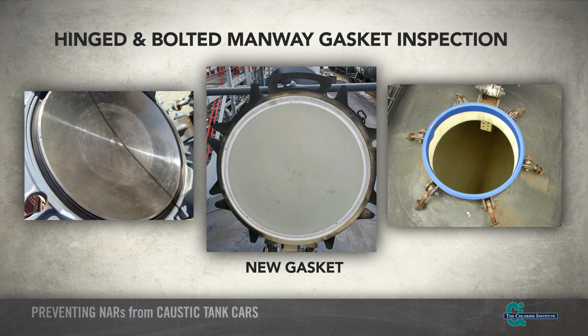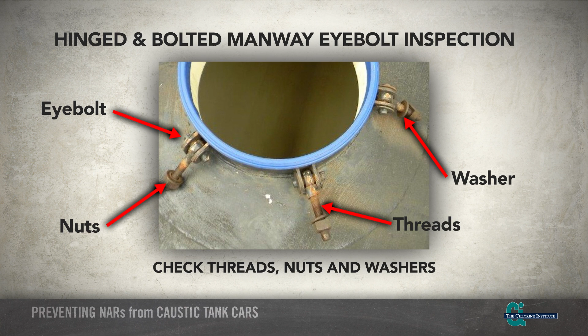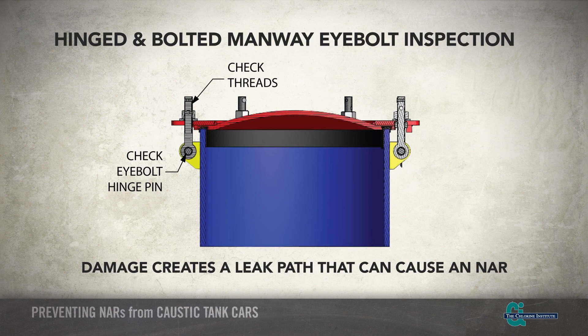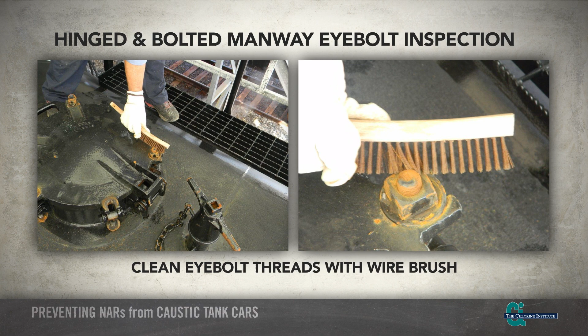Prior to closing the hinged and bolted manway, it's crucial to inspect all of the manway eye bolts, including the safety eye bolt at the manway handle and eye bolt threads, nuts, and washers. If any one of the eye bolts or nuts are damaged, have dirty or damaged threads, or if the washers are damaged, it creates another leak path that can result in an NAR. A wire brush may be used to remove debris from the eye bolt threads for a close inspection.